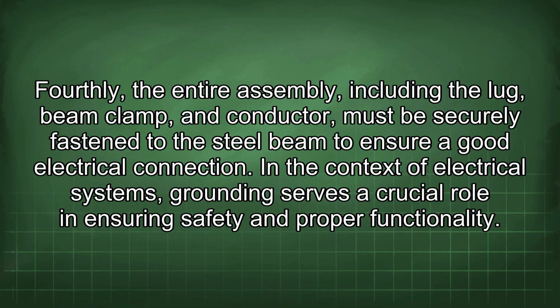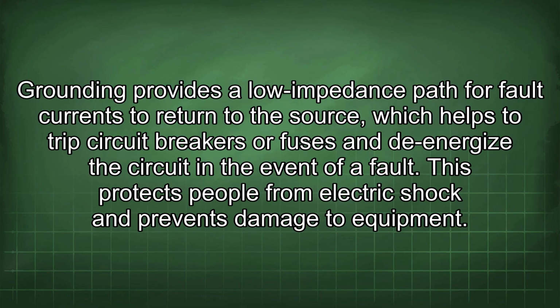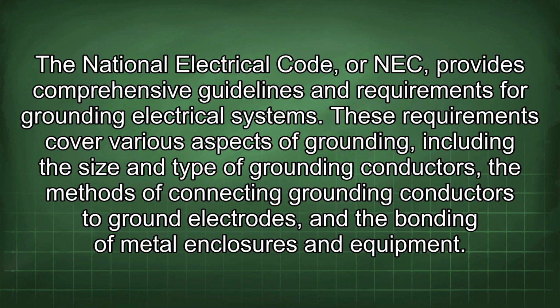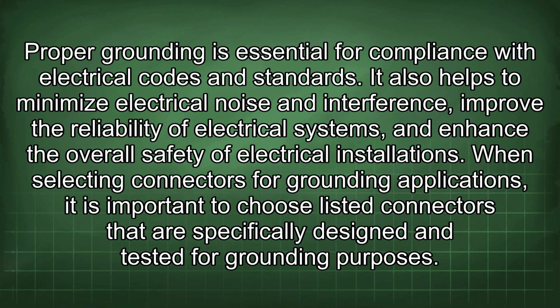In the context of electrical systems, grounding serves a crucial role in ensuring safety and proper functionality. Grounding provides a low impedance path for fault currents to return to the source, which helps to trip circuit breakers or fuses and de-energize the circuit in the event of a fault. This protects people from electric shock and prevents damage to equipment. The National Electrical Code, or NEC, provides comprehensive guidelines and requirements for grounding electrical systems. These requirements cover various aspects of grounding, including the size and type of grounding conductors, the methods of connecting grounding conductors to ground electrodes, and the bonding of metal enclosures and equipment. Proper grounding is essential for compliance with electrical codes and standards.